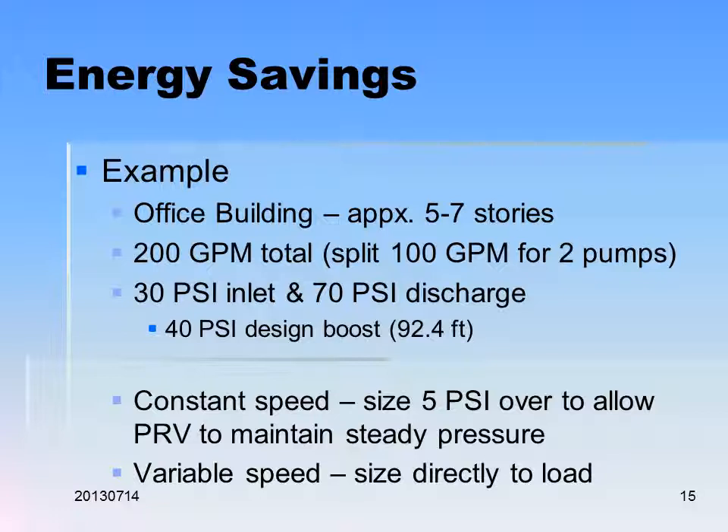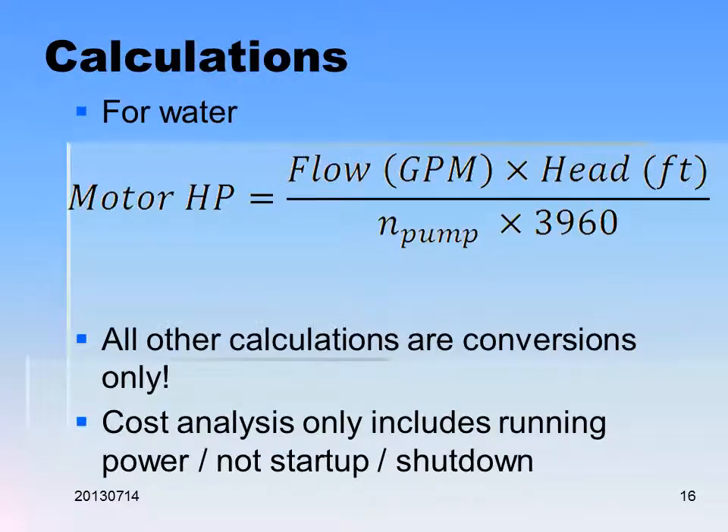Here's an example of an office building approximately five to seven stories: 200 GPM total, split between two pumps at 100 GPM each, 30 PSI on the suction, and 70 PSI discharge — that's a 40 PSI boost, which equates to 92.4 feet. For constant speed, size with 5 PSI over to allow the PRV to maintain steady pressure due to the pressure drop in the PRV. For motor horsepower, take the flow in GPM times the head divided by the efficiency of the pump times 3960. Other calculations are for conversions only. The cost analysis includes running power only.